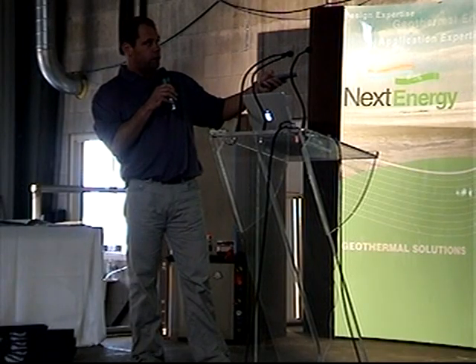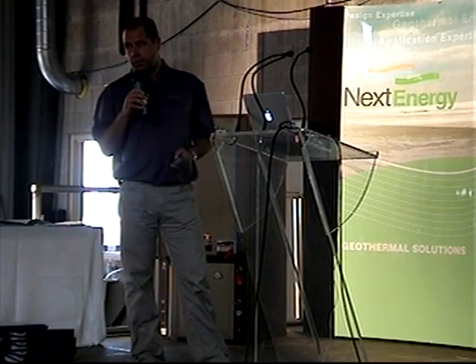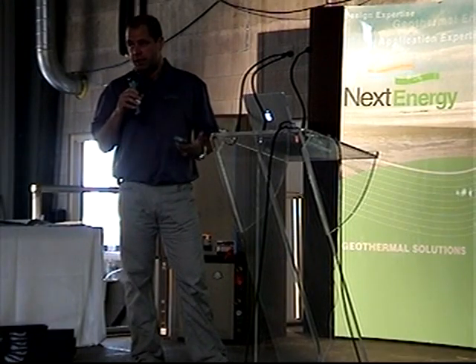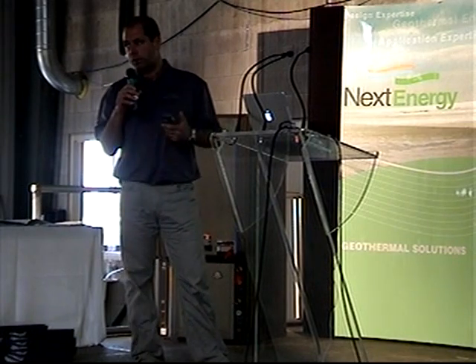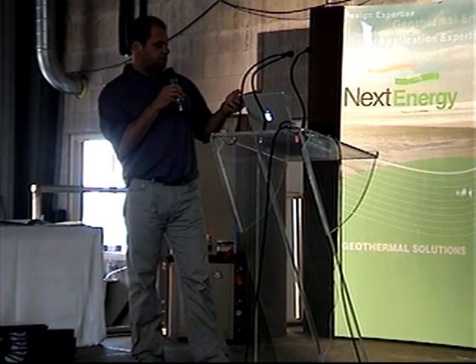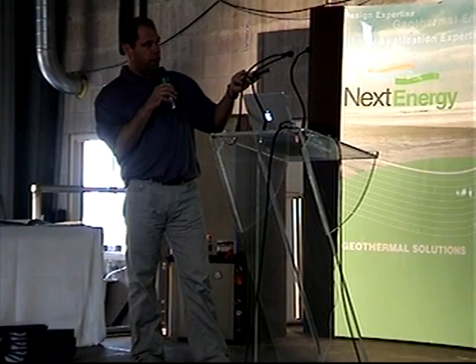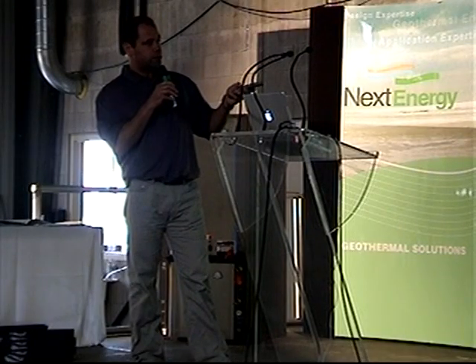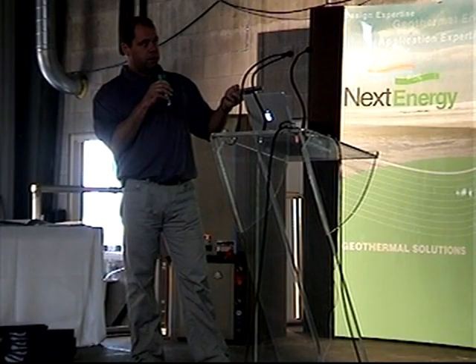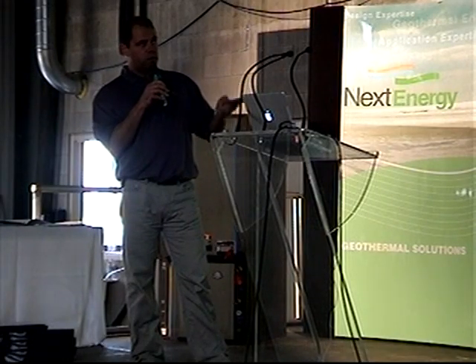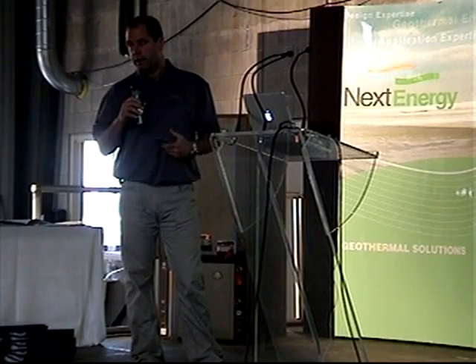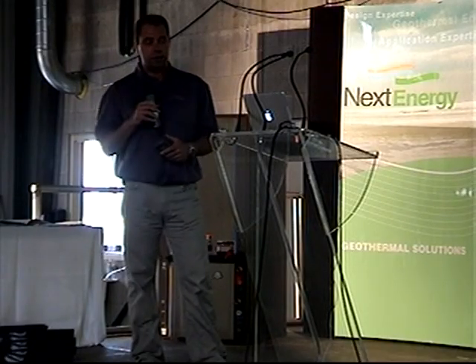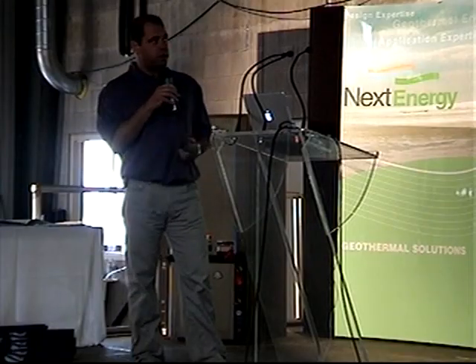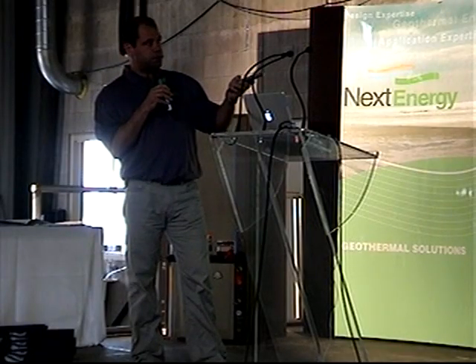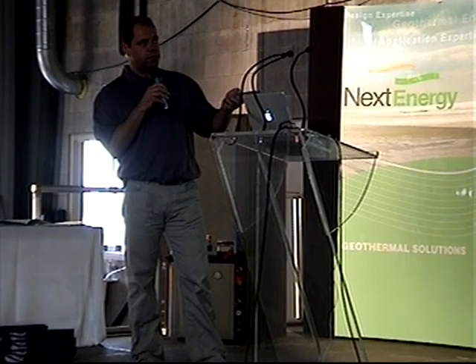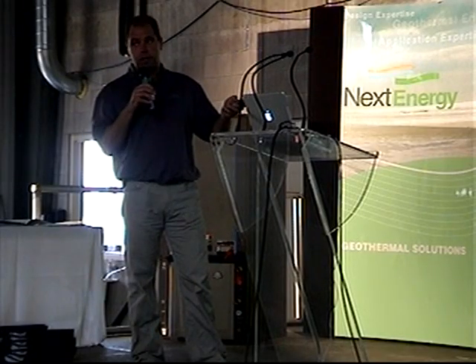This here represents water. It takes 1 BTU. Well, a BTU is how much energy is required to change 1 pound of water 1 degree. As you can see here, water is going from 209, 210, 211, so that would be 2 BTUs. But to go from 211 to 212 means the water has to actually boil, and that's our latent heat, and that's where refrigeration is all about. It takes 970 BTUs to go from 211 degrees to 212 because it has to change state.